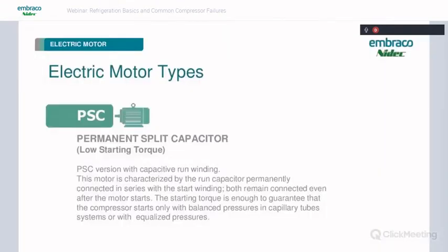And then we have a PSC. This is more of your air conditioning motor. PSC stands for permanent split capacitor. So it has a capacitor that's actually mounted in the start winding. So basically both windings are energized at all times. But this added run capacitor, it's still a low starting torque motor, but the addition of this run capacitor gives it just enough torque to start with a fixed orifice. Since we're talking about air conditioning, you're talking about a piston typically.